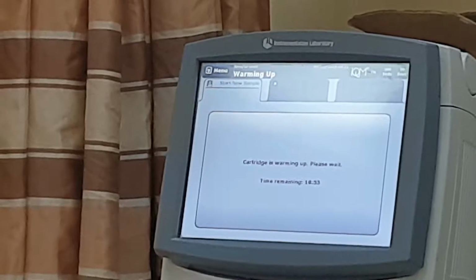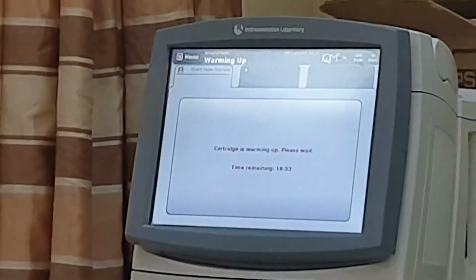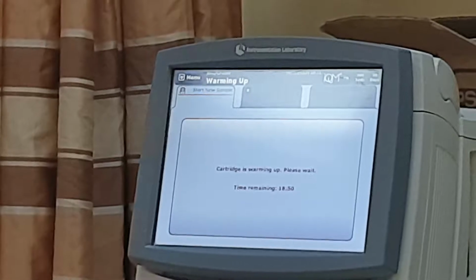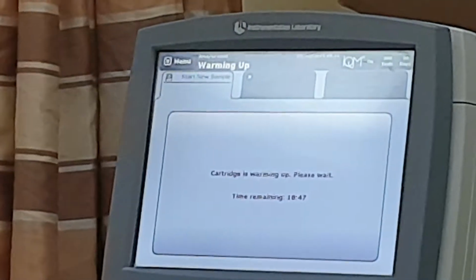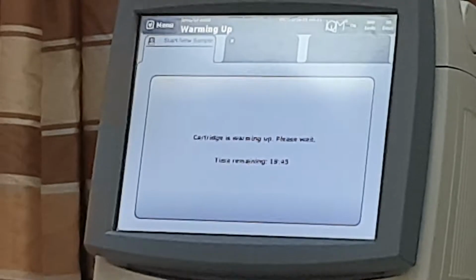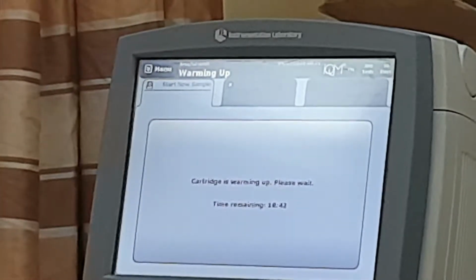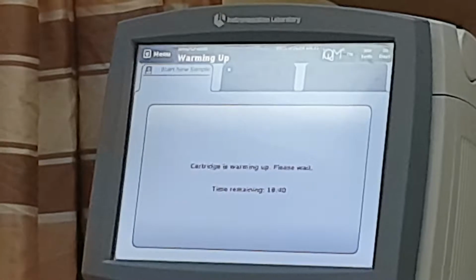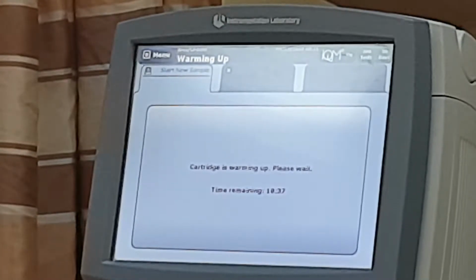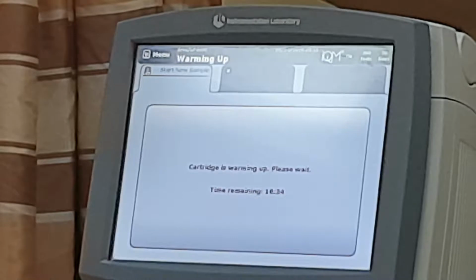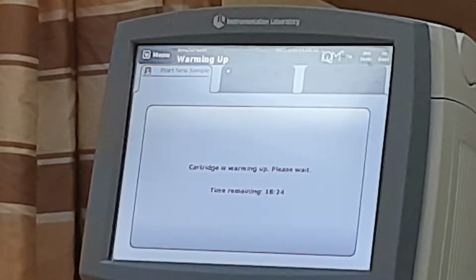We will only consume the number of calibrations. We have 4 levels of calibration. Once we change the cartridge, we have to run the calibration just one time. That cartridge should be kept at room temperature, not in the refrigerator. Stability is 30 days once I insert it inside the machine, whether I consume the number of tests or not. After 30 days, it will open the door. We have 300 tests.